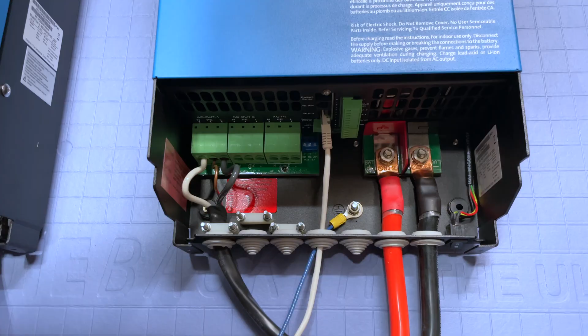Coming around to the connection, let's talk about this. This right here is your AC1 block, here is your AC2 block, and here is your AC in. This white cable is your standard Ethernet cable, connected to VE bus, and the other end connects to the other unit on VE bus. This connection is your inverter ground, connected with 10 gauge wire to the other ground points on the system. This right here is obviously your DC in.